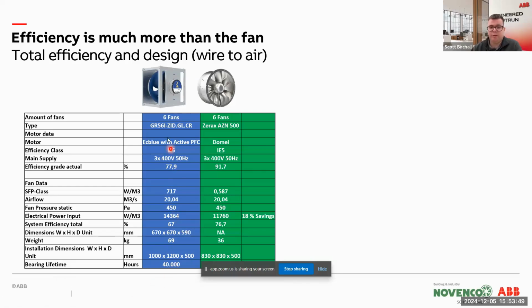The other interesting one is the bearing lifetime. In the manual for these fans, it shows 40,000 hours, and that's at 40 degrees C. Sometimes these are running hotter than that and it can be less. The manual says you need to replace these at that time, which ends up being the whole unit being replaced. So the operating time for these is not really as long as you would expect.